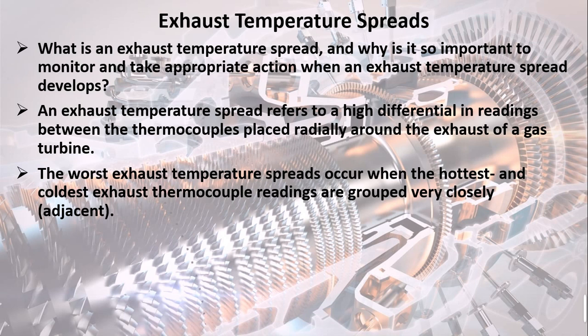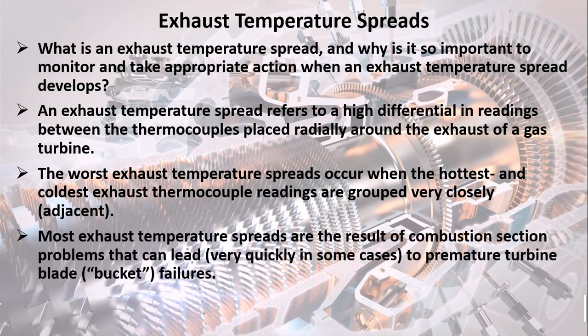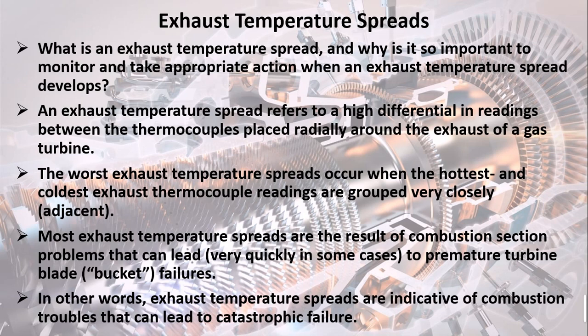The worst exhaust temperature spreads occur when the hottest and coldest exhaust thermocouple readings are grouped very closely adjacent. Most exhaust temperature spreads are the result of combustion section problems that can lead, very quickly in some cases, to premature turbine blade and bucket failures. In other words, exhaust temperature spreads are indicative of combustion troubles that can lead to catastrophic failure.